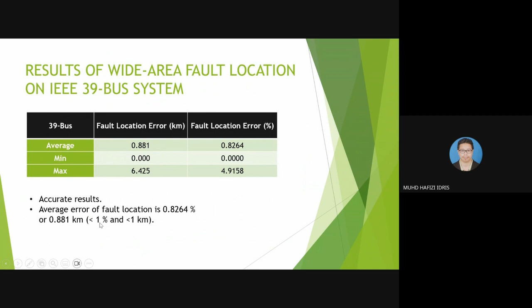We also tested the methods on different line lengths in the network to see whether the method is affected by the charging current or not. From the test, the proposed method, where we choose the negative sequence values as the input, was not affected by the charging current of different line lengths compared to the method where we choose the positive sequence values as the input.